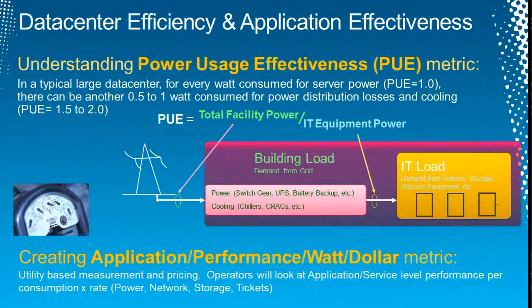So let's talk about a couple of measurements, then I'll get into the data center stuff, which is the fun part. Everybody probably understands power utilization efficiency—let me clarify it: building load over IT load. If we have a PUE of 2, that means I've got 2 megawatts running at the building level and 1 megawatt at the IT level. That's not very good, not very efficient.